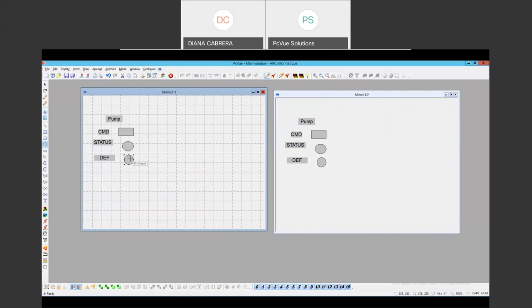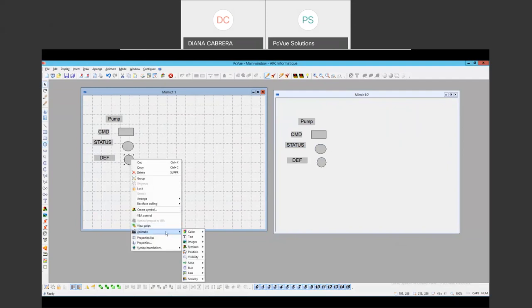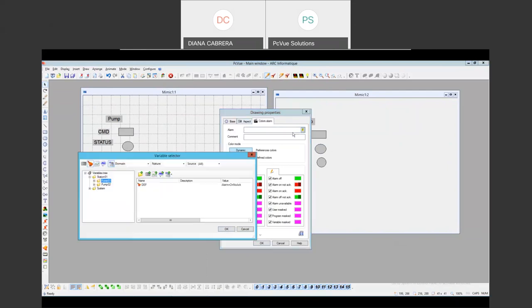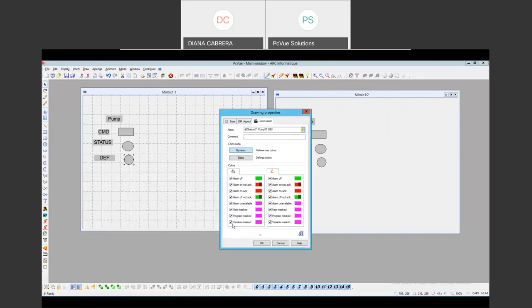I also want to show you a new animation called color alarm. I have a new tab with different properties. I'm going to look for my variable 'default'. Here we can see that we have the color mode: dynamic or static. Dynamic means it will take the color of our project; static means it takes the color we define here — when the alarm is off, on not acknowledged, on acknowledged, and so on.